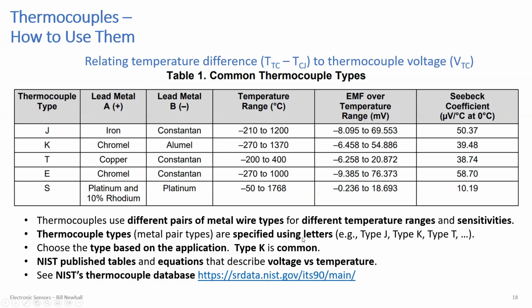All right, let's take a look at this. Before I go to a plot, look at this Seebeck coefficient. That's really small, microvolts per degree C. That implies you have some linear characteristic, because you're given a slope here, but at a specific temperature, which implies looking to the future that you're probably going to have some nonlinearities there. But look at how small that coefficient is in microvolts per degree C, and then look at the total range over the temperature range.